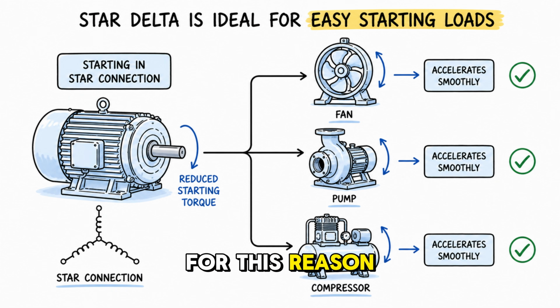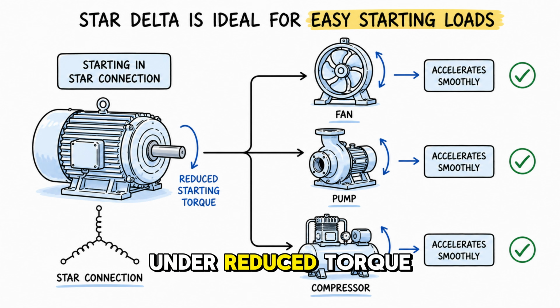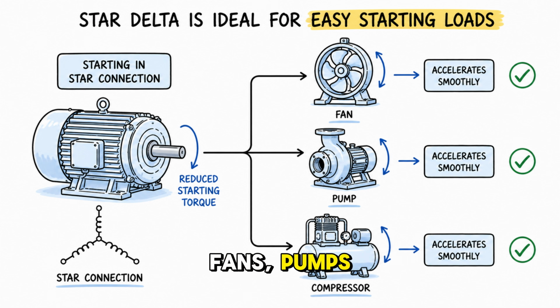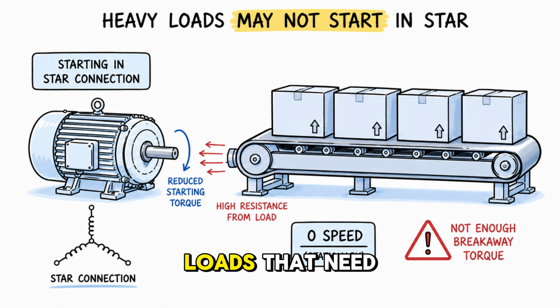For this reason, star-delta starting is only suitable for loads that can easily accelerate under reduced torque. Fans, pumps, and compressors are ideal. Loads that need high torque to break away from rest, like heavily loaded conveyors, cannot use star-delta because the reduced starting torque may not be enough to move the load at all.